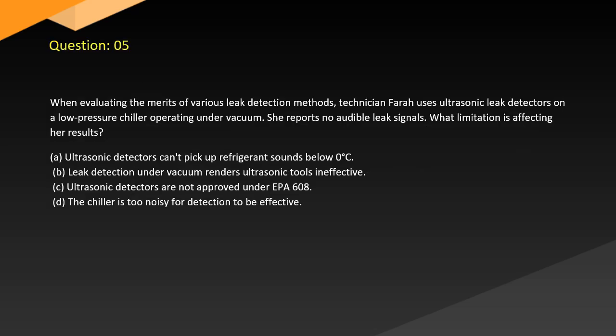Question 5. When evaluating the merits of various leak detection methods, technician Farah uses an ultrasonic leak detector on a low-pressure chiller operating under vacuum. She reports no audible leak signals. What limitation is affecting her results? A. Ultrasonic detectors can't pick up refrigerant sounds below 0°. B. Leak detection under vacuum renders ultrasonic tools ineffective. C. Ultrasonic detectors are not approved under EPA 608. D. The chiller is too noisy for detection to be effective.